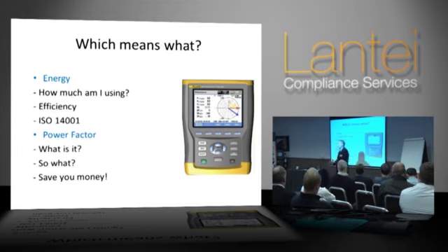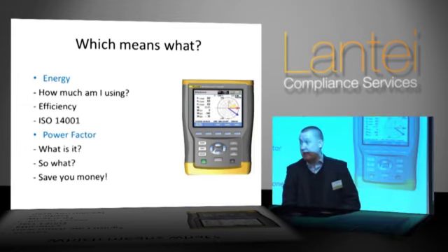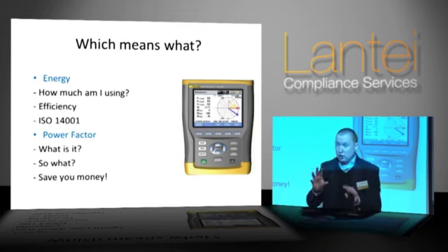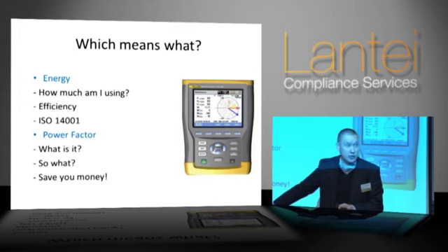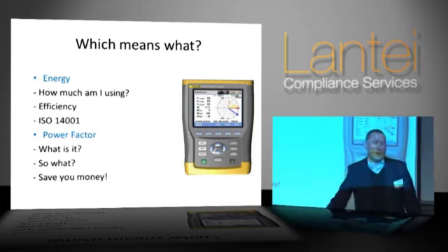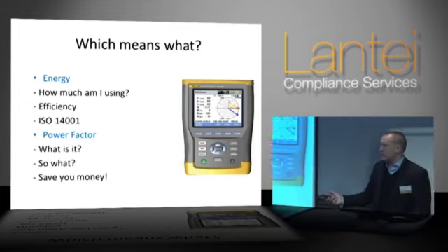But when we've got poor power factor correction within our electrical installations, that equipment also needs what we call reactive power to make it work. So to put it another way, we're using two lots of energy, one of which, if we improved our power factor, we wouldn't need to use - i.e. we're spending more than what we need to be spending. That's another thing mains analysis will do for us.